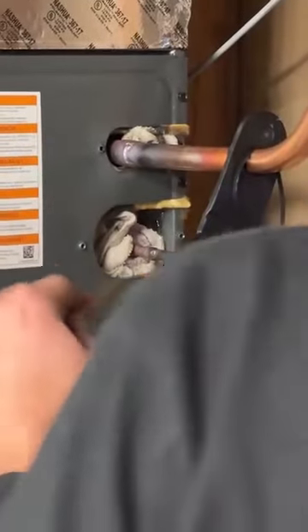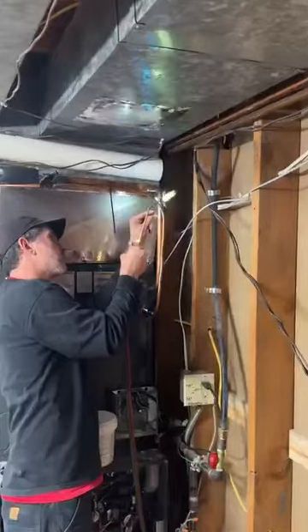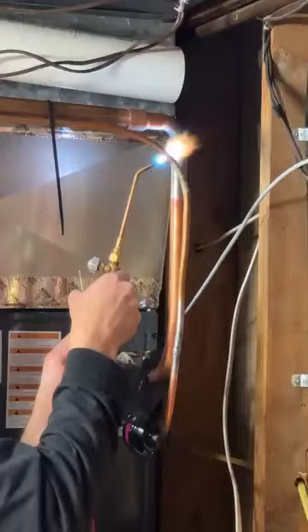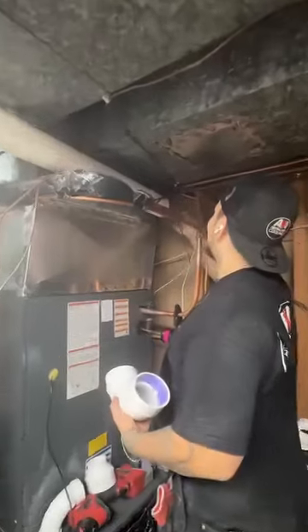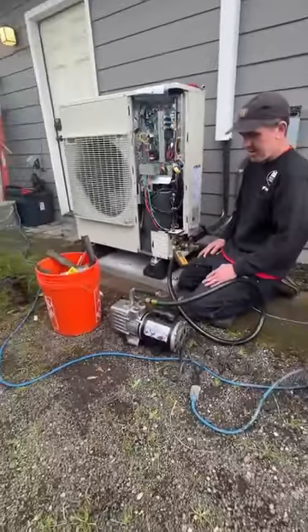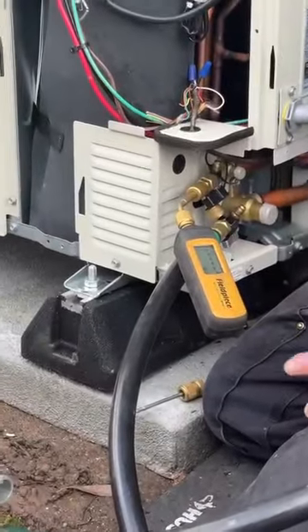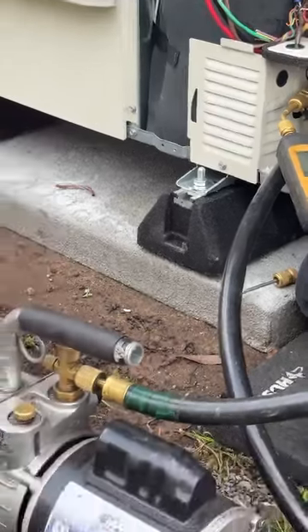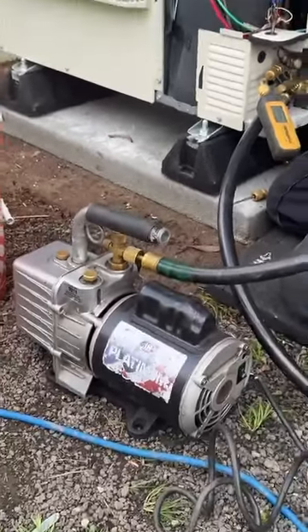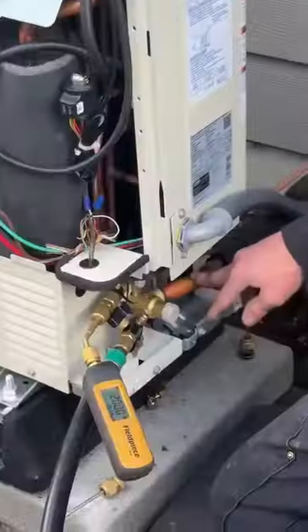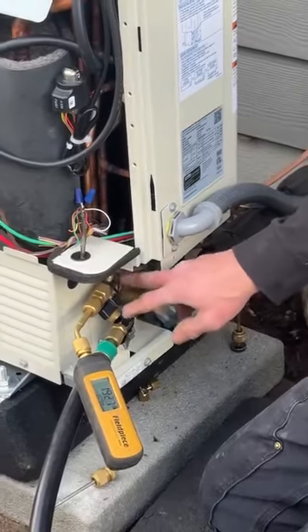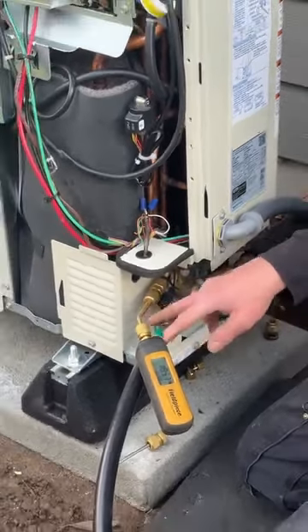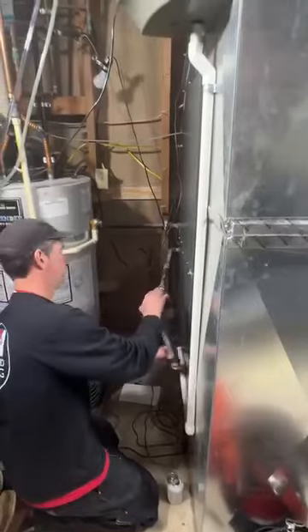A small black filter is installed on the line as well to help catch any moisture or particulates that could obstruct the flow of the line. With the brazing done, we can now complete the exhaust piping for a full connected pipe. Meanwhile, outside, after performing a 30-minute pressure test, and now that we are confident there are no leaks in our weld work, we put on a vacuum pump and a micron gauge and suck the line down to under 500 microns, which we run for about an hour. Then we drill a hole for the natural gas line and begin to install the new line.